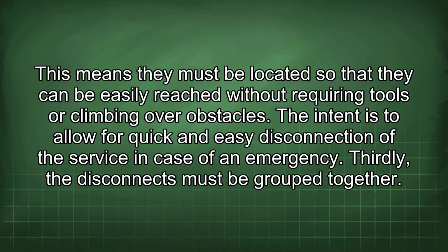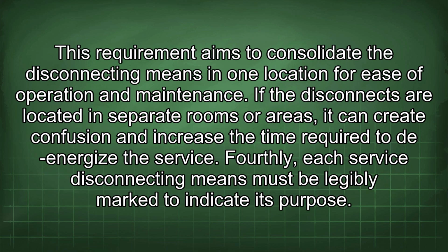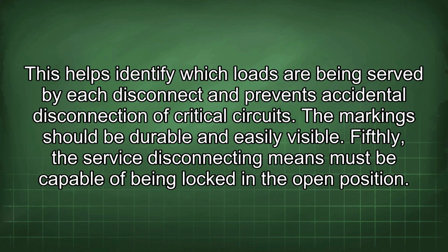Thirdly, the disconnects must be grouped together. This requirement aims to consolidate the disconnecting means in one location for ease of operation and maintenance. If the disconnects are located in separate rooms or areas, it can create confusion and increase the time required to de-energize the service. Fourthly, each service disconnecting means must be legibly marked to indicate its purpose. This helps identify which loads are being served by each disconnect and prevents accidental disconnection of critical circuits. The marking should be durable and easily visible.